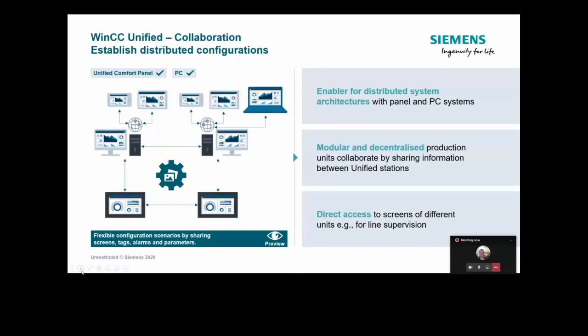Another option mentioned is the concept of collaboration — this is unique to WinCC Unified. This allows multiple different WinCC Unified systems to collaborate with each other. For example, we might have four different WinCC Unified systems: two PC-based with their own individual clients, and two panel-based Unified Comfort systems. The collaboration option — a licensed option on each station — allows us to share data between the different stations. For instance, sharing screens.